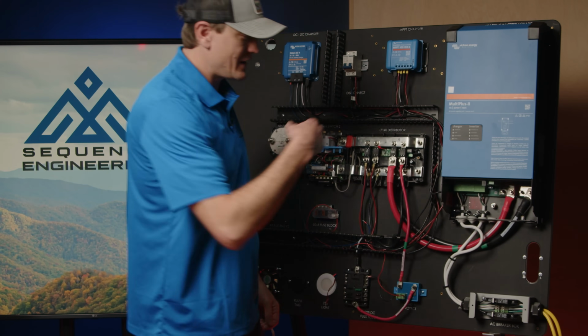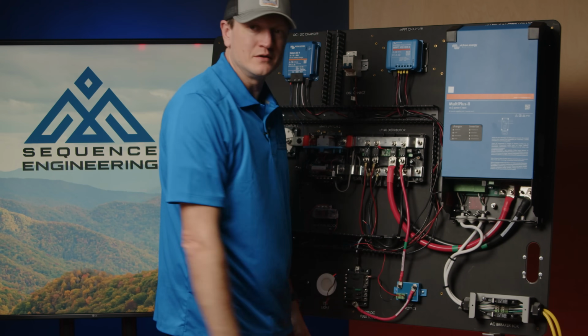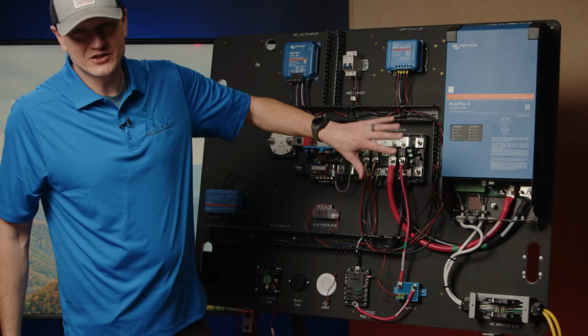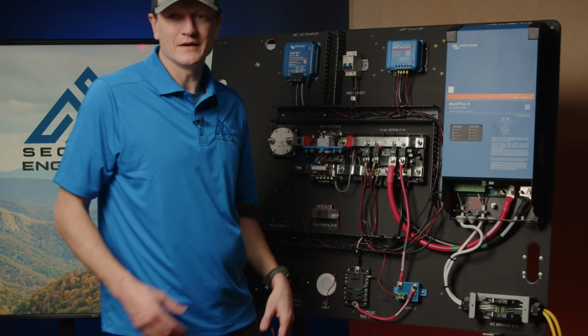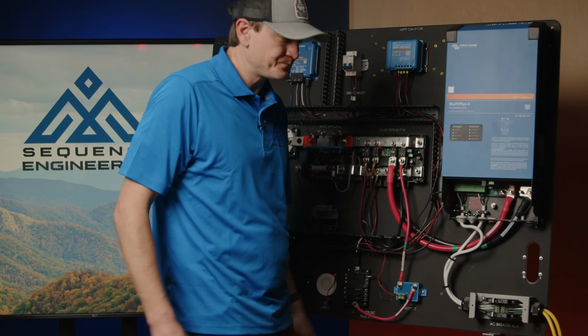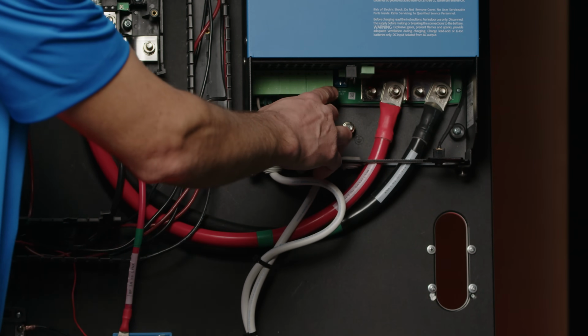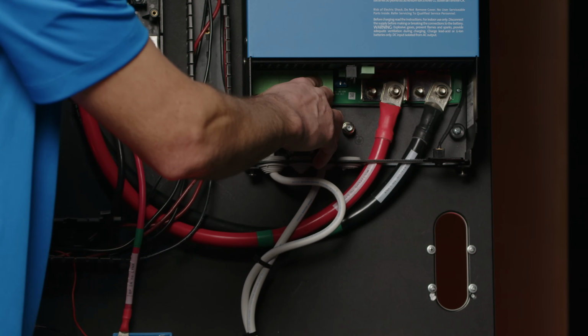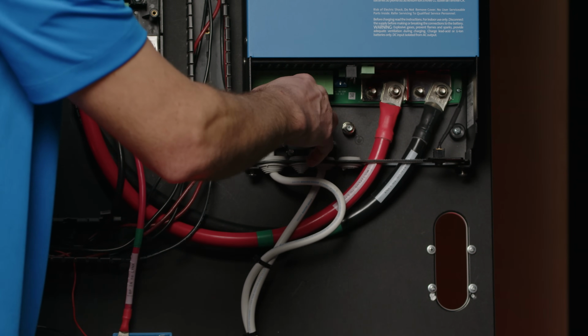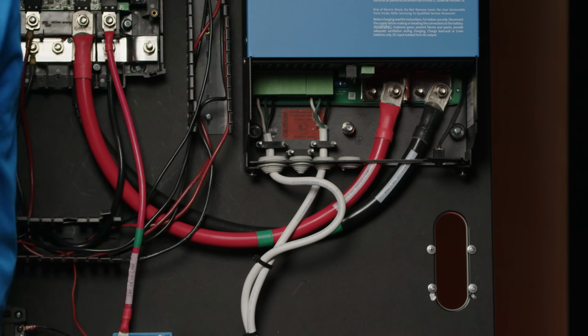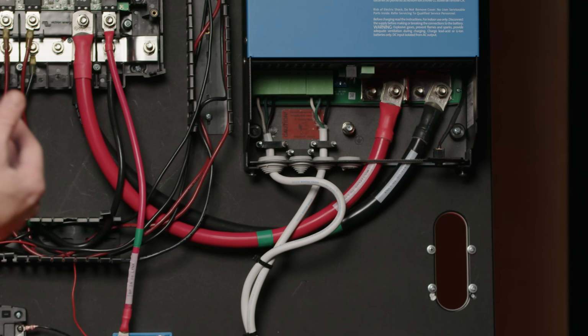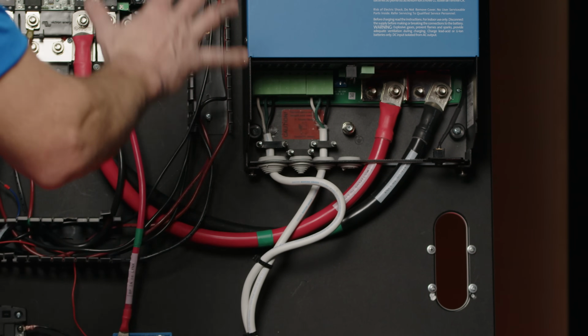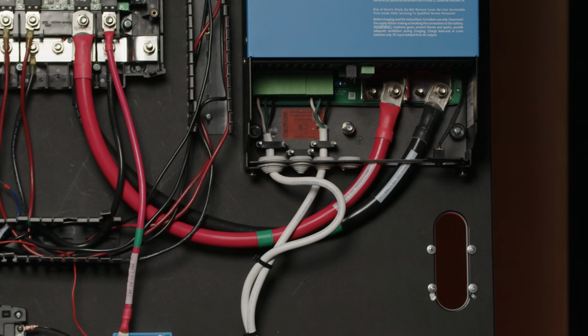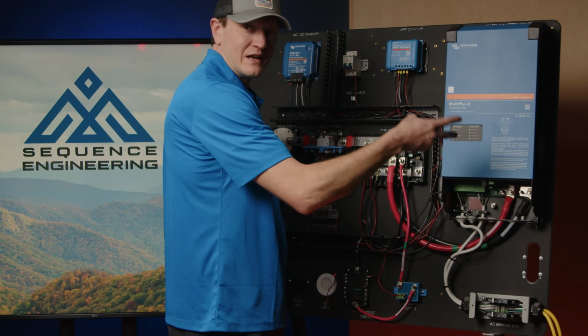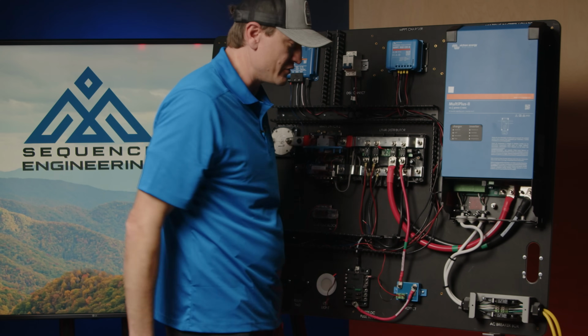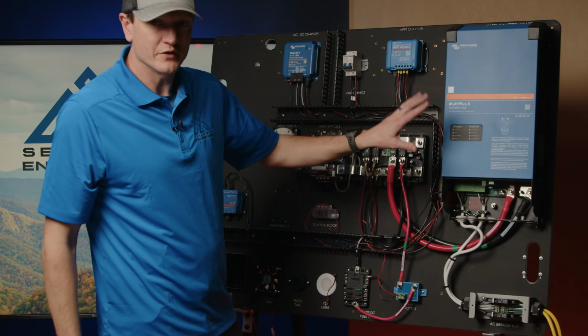Now that I have AC in and AC out wired, I'll cover a few more things about wiring this up and how it functions. We have AC in over here - line, PE which is your ground, and N which is your neutral. They are clearly labeled, and you need to make sure those wires are in the correct location before you power this on. That's one thing that could cause heartache - if you get line and neutral mixed up, you do not want to wire this in reverse polarity.